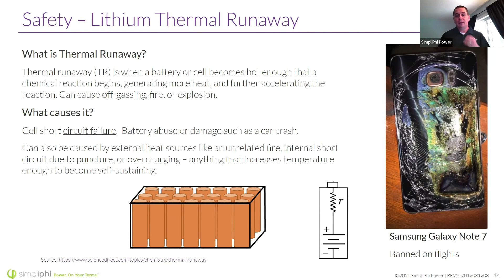So let's talk about the numbers of thermal runaway. We've talked about what happens. There's going to be vaporizing of the electrolyte, causing some off-gassing. That gas is contained, great. But if it escapes, it's toxic and flammable. Now, lithium iron phosphate, or LFP, can reach a higher temperature than an NMC battery or other cobalt-based batteries before thermal runaway begins. That's a ballpark of about 200 degrees centigrade for LFP to reach thermal runaway.